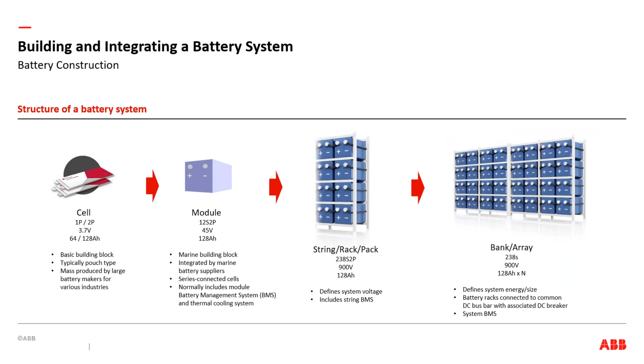I won't get into deep discussion on this slide—just suffice it to say battery sizing isn't as obvious as it might first seem. You might look at a project and say, okay, I have a ferry, she crosses back and forth, I need 300 kilowatt hours to get across, so therefore I need a 300 kilowatt hour battery. Not exactly. There are a lot of factors that come into play, most significantly the number of cycles and the life of the battery, but also the power demand—what's the highest power we're going to need from the battery—and some other factors.